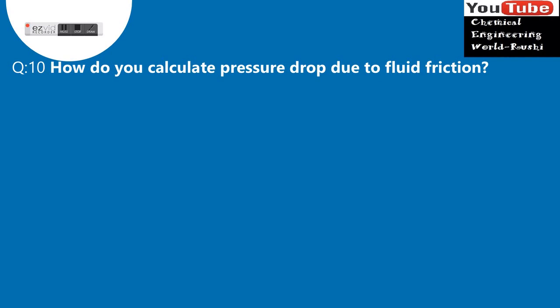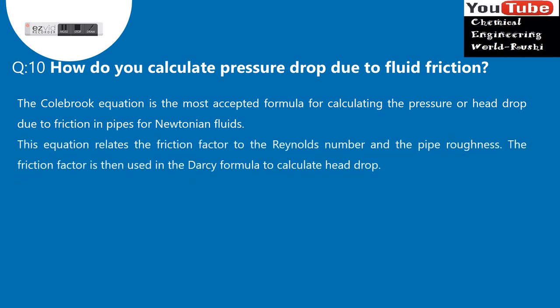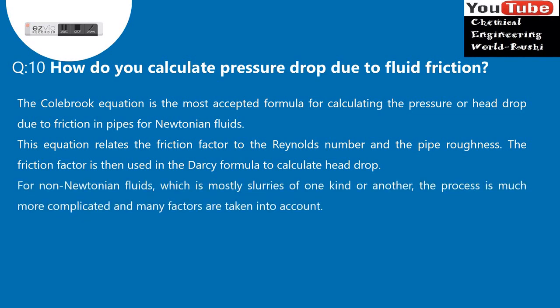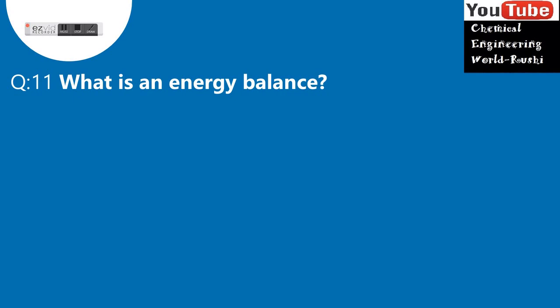Question 10: How do you calculate pressure drop due to fluid friction? The Colebrook equation is the most accepted formula for calculating the pressure or head drop due to friction in pipes for Newtonian fluids. This equation relates the friction factor to the Reynolds number and the pipe roughness. The friction factor is then used in the Darcy formula to calculate head drop. For non-Newtonian fluids, which are mostly slurries of one kind or another, the process is much more complicated. Some factors taken into account are: particle size and distribution, settling velocity of particles in the mixture, viscosity variation of the mixture, and solids transportation mode.